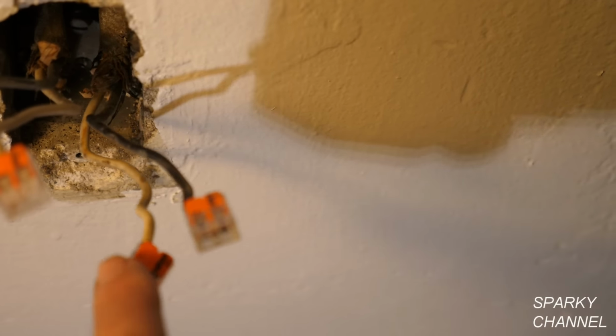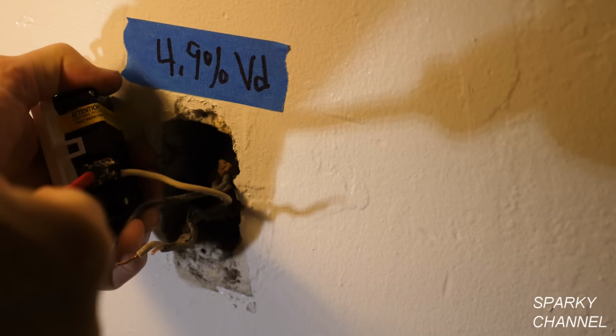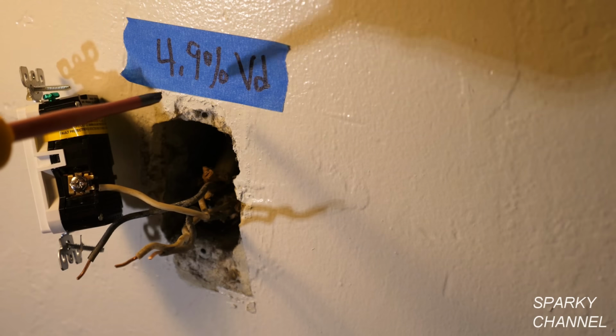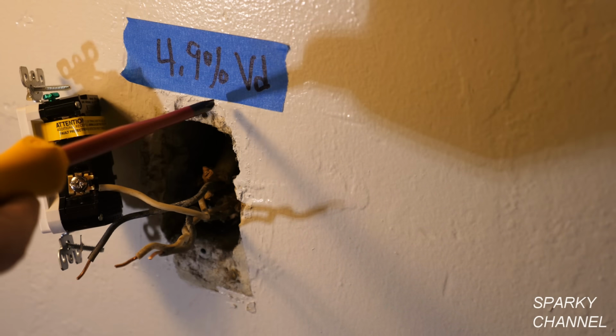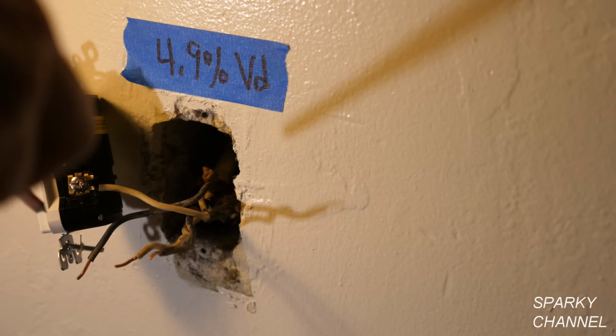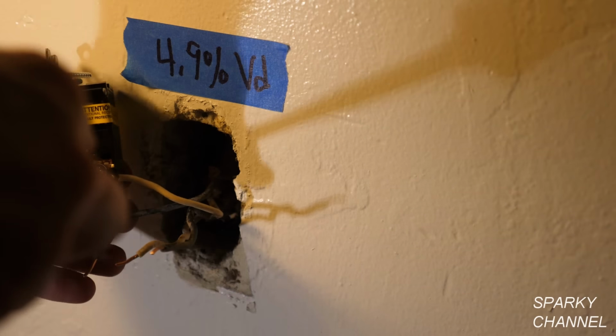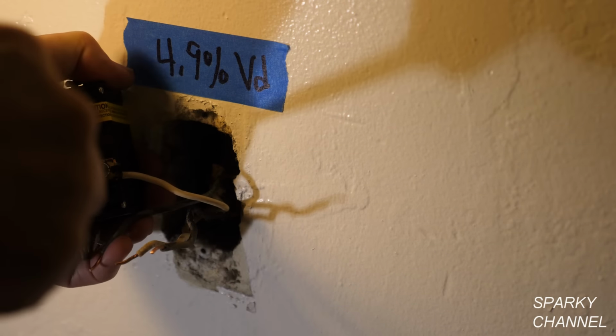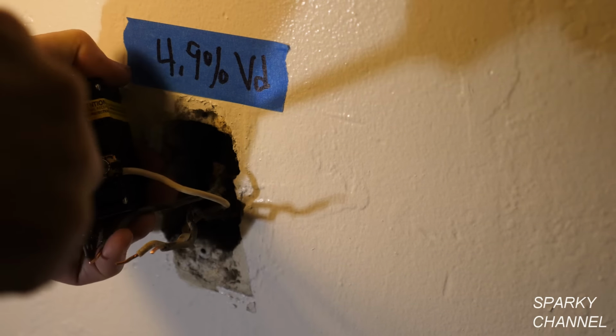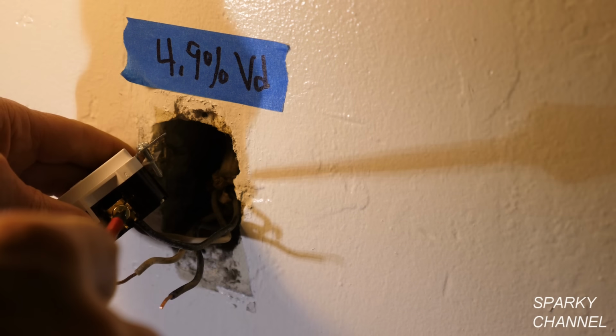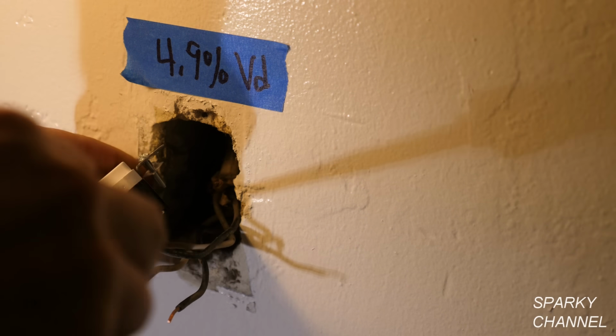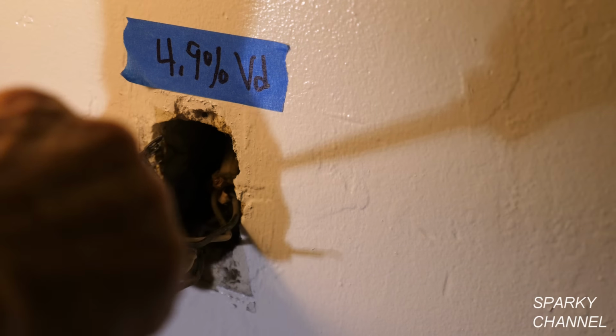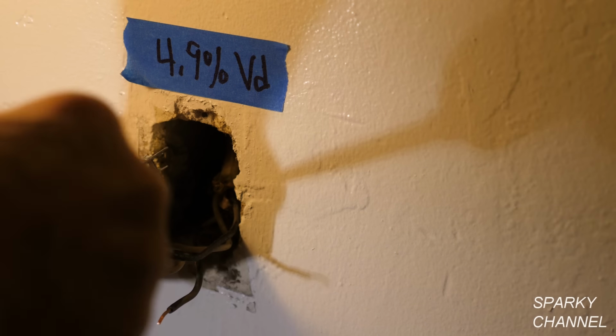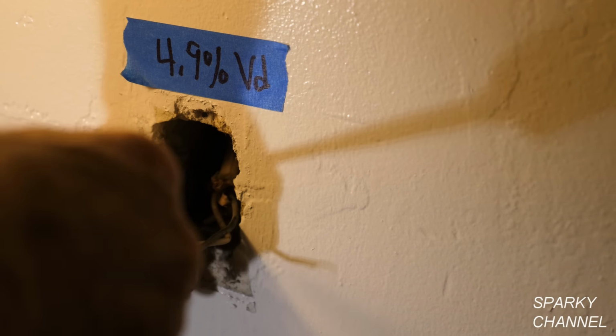And I'll tighten it up securely. I'm going to want to make all these connections very secure, because even though we started out with 4.9% voltage drop, it got a lot higher as the circuit went along. So now I'm going to put the hot wire in on the brass colored side. I'm going to tighten that up real good. So every connection, I try to make real solid.